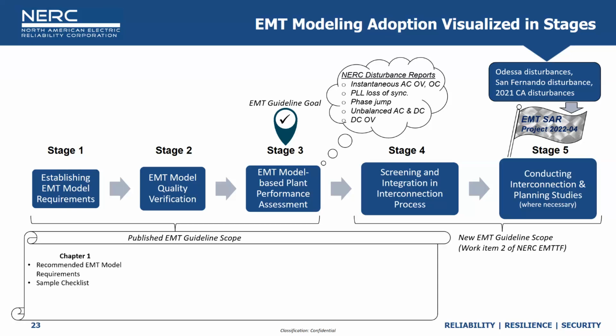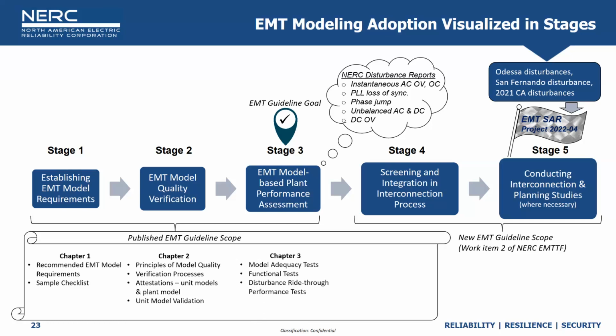So, the guideline that we're talking about today: chapter one covers the recommended EMT model requirements. We even provided a sample checklist. Chapter two covers principles of model quality. So we're really trying to align our industry on the expected requirements and expectations around what it means to be model quality, and how to verify those principles of model quality using attestations and documentation to establish that, as well as unit model validation reports. Chapter three gets into the model adequacy test, functional tests, and disturbance ride-through performance tests. So you can see they loosely model after the first three stages. And we try to get a little bit into stage four by covering the EMT study use cases, common situations needed in the EMT study.